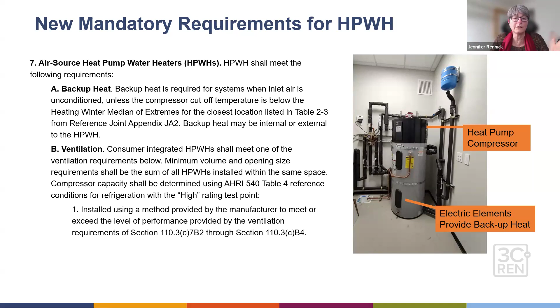Now in these mandatory measures, they're really spelling out that if you have a heat pump water heater with no ducts, you need to follow requirements for how the space can communicate to a larger volume. In this case, the heat pump water heater was installed in a closet with a louvered door. It's okay to use the louvered door, but now we have to calculate the net free area of the louvered door and see if it's large enough, or follow the manufacturer's specifications. And there are other qualifications on where those openings can be located. That ties back into the theme that the code now includes a definition for net free area, specifically for how you calculate it with louvers or slats.